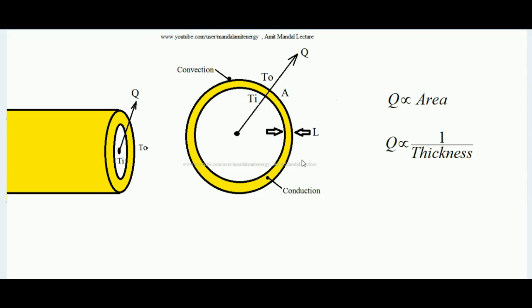We know that heat transfer rate q is proportional to the area of exposure through which heat is transferring. For this case, heat transfer rate is also inversely proportional to the thickness of insulation, because greater the thickness of insulation, greater the resistance in the path of heat transfer. So greater the outer peripheral area of exposure, greater the heat transfer rate delivered to the environment; and greater the thickness of insulation, lesser the heat transfer.